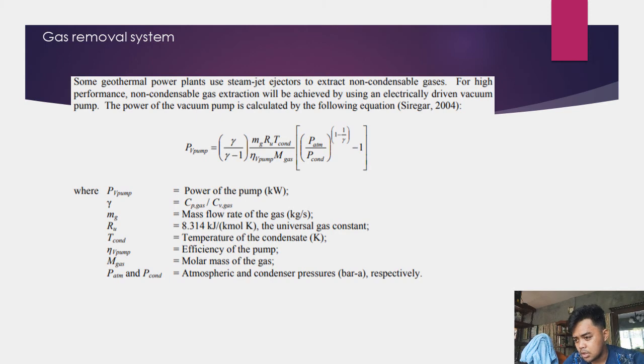Gamma is equal to the heat capacity ratio, Cp gas over Cv gas. M sub G is equal to the mass flow rate of the gas in kilograms per second. R sub U is equal to 8.314 kilojoules per kmol Kelvin, the universal gas constant. T con is equal to the temperature of the condensate in Kelvin. Eta sub V pump is equal to the efficiency of the pump. M sub gas is equal to the molar mass of the gas. P atmospheric and P condenser are the atmospheric and condenser pressure respectively.